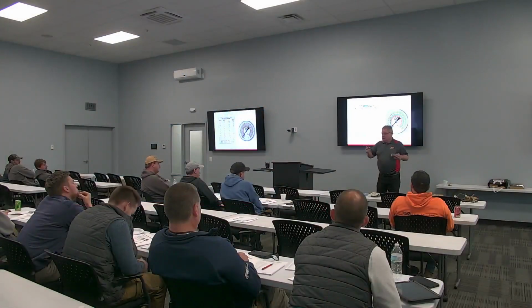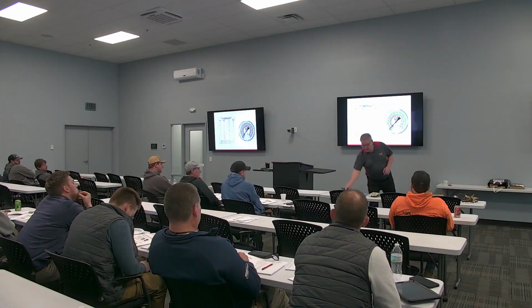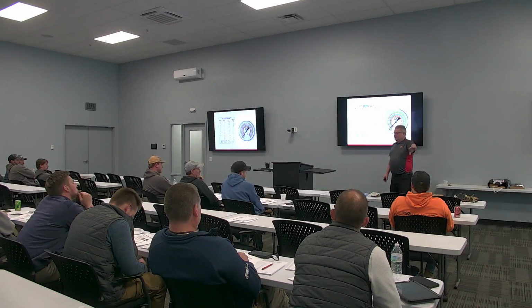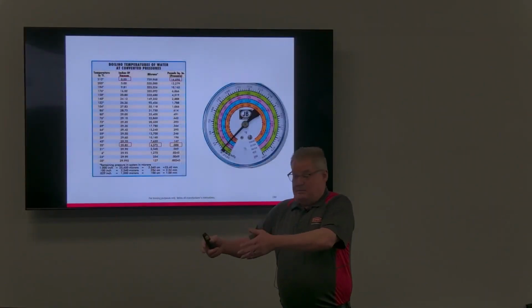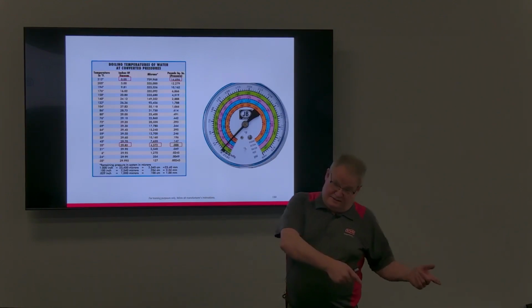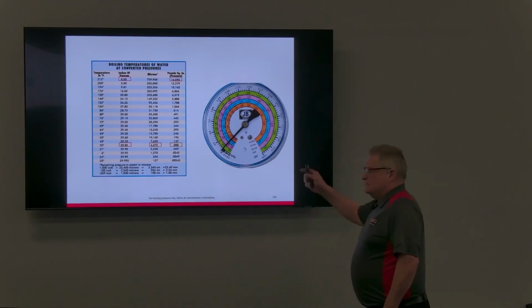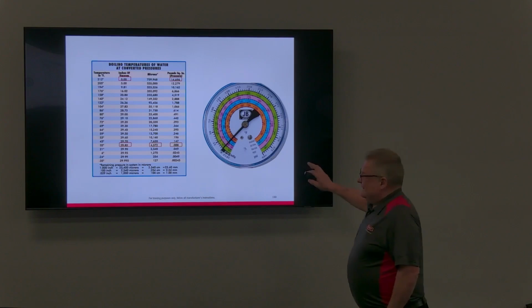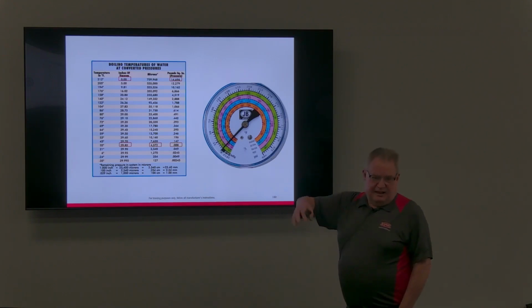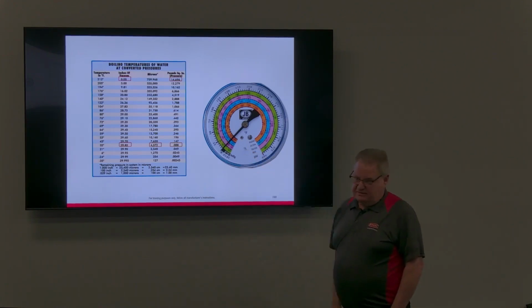Really pretty cool. We do have one, and you might have 1,800 microns at the system yet that pump is reading 200. Because what it's reading on the pump, I might have 200 at the pump, but not necessarily in the system. So this is a really important thing we do. The advent of all these digital gauges really helps us do our job better, and the micron gauge tells us what's going on in the system.